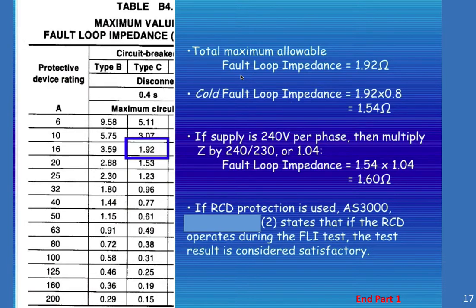So you can see here our fault loop impedance, the maximum available, 1.92 ohms. Our cold fault loop impedance is 1.92 times 0.8. So if the supply voltage is 240 volts per phase, then we multiply the Z by 240 or 230 or 1.04. So the earth loop impedance would be 1.54 multiplied by 1.04 equaling 1.6 ohms.